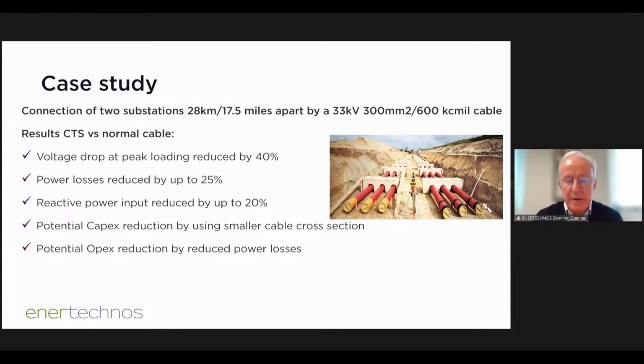We've been developing the cable over the last 9 years. It's now 4 years since the first commercial batch was made, in 2 European factories: one was Cabelte in Portugal, the other Tratos in Italy. Those cables are all designed for up to 33 kV with a 300 square millimeter cross-sectional area.